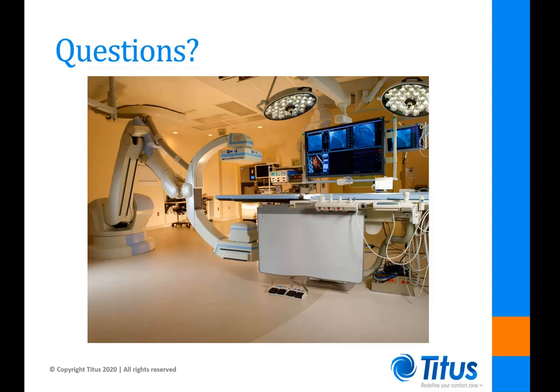The next question is: should you use laminar flow diffusers with filters in operating rooms? The short answer is yes, absolutely. It's always ideal to have HEPA filtered supply air in an operating room to minimize the number of particles potentially coming into contact with the patient. Ideally, you're using a point-of-service HEPA filter to ensure the air entering the space is as clean as possible. If that's not practical due to change-out maintenance requirements, the next best option is to have a terminal HEPA filter module in the hallway outside the operating room on the main branch duct.